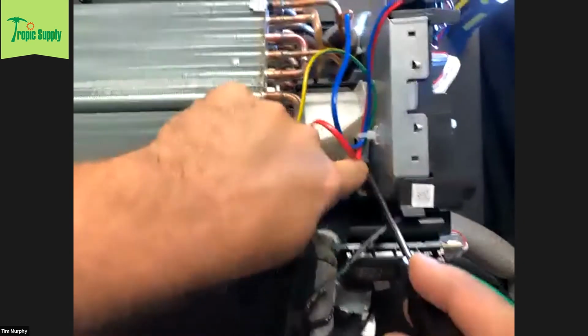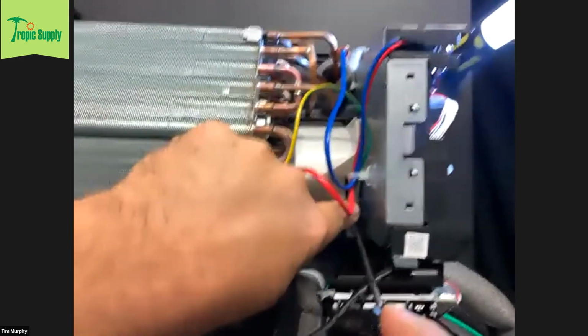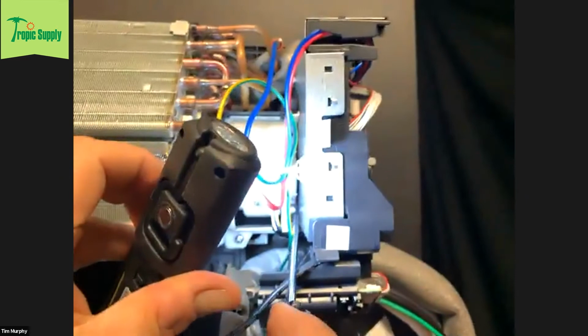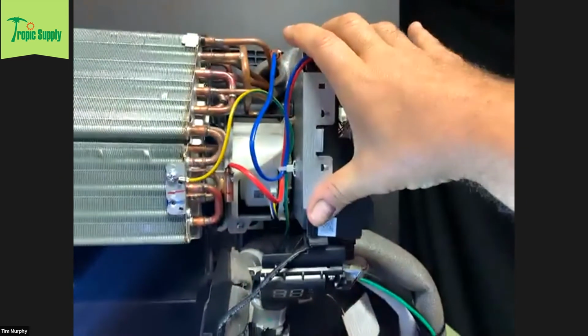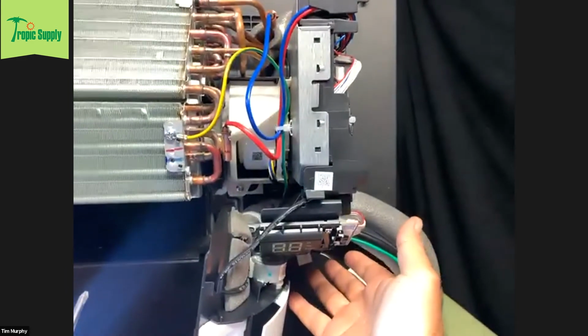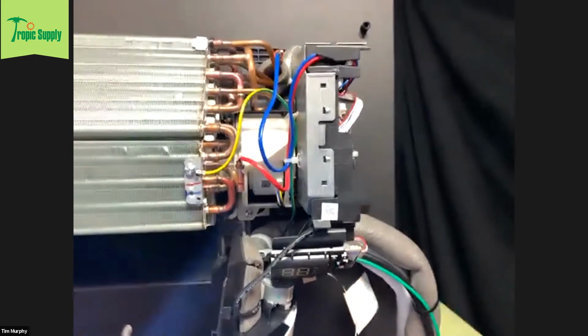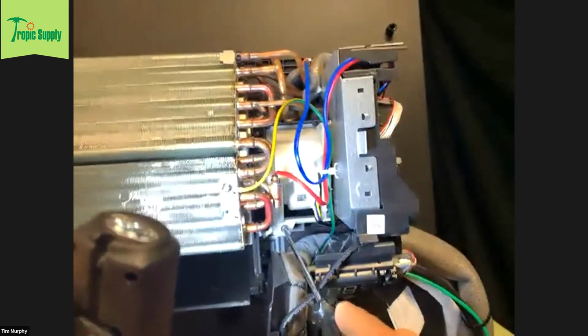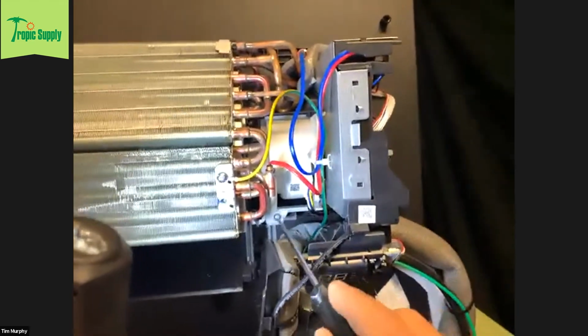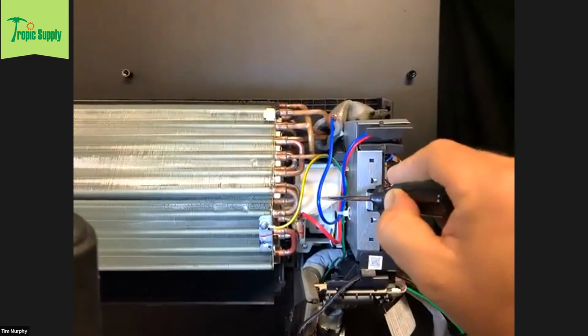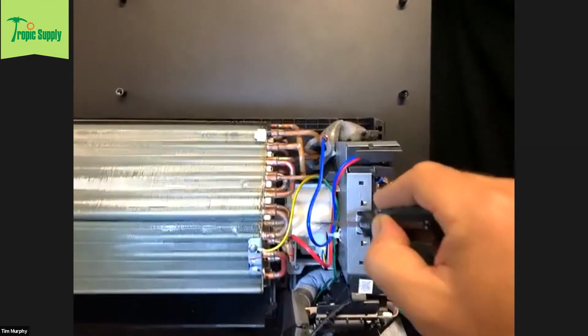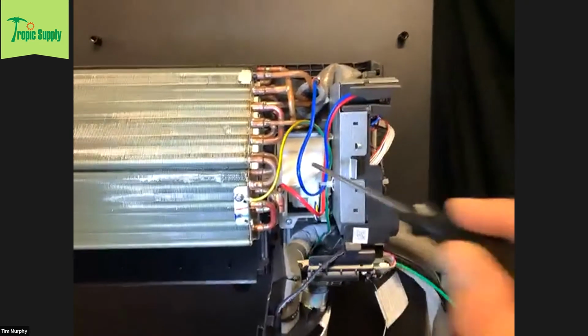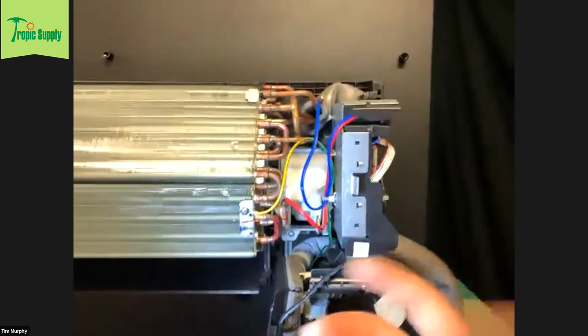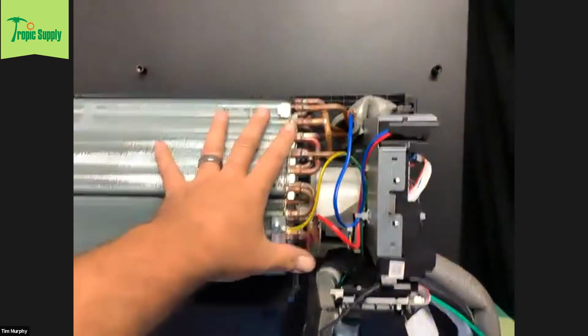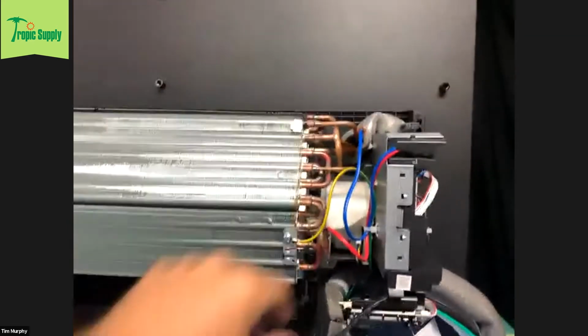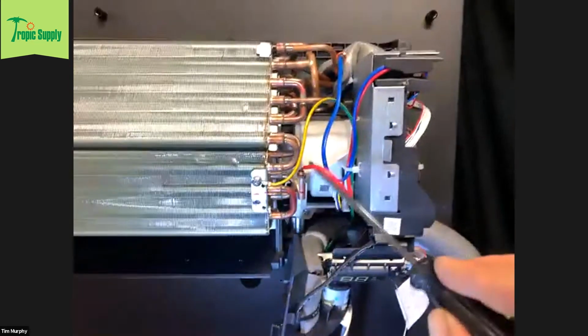There's one set screw back here. I'm not going to remove it, but there's one set screw here. Let me see if I can get a shot. You can see there's a set screw back in there. You take that one set screw out and this whole unit will come completely off. Obviously, you'll have to disconnect your line voltage and control wire first. Once you remove that, this one screw is what helps you remove this. If you've ever had to remove a fan motor on one of these mini split systems, you know how daunting it can be. When you take this screw off, this cover basically comes right out and you get the motor in your hand without having to pry the coil way up, like you have to on a lot of other systems to get access to that blower motor. You don't have to here. Just that one screw, and this comes right out.